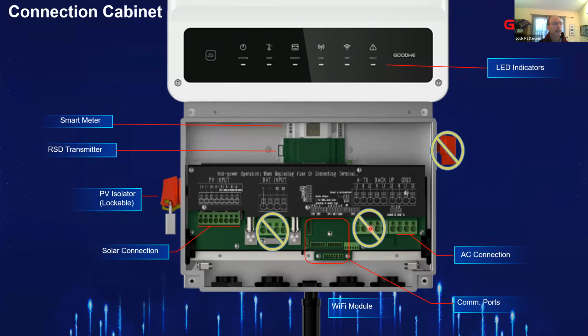Same on the right side. You wouldn't do the AC backup circuit connections. We're only concerned with the AC grid connection on the right. So your L1, L2, neutral. And then for each side, we have grounding equipment grounds. So there's a bus bar here and a bus bar here with set screws. And those are the only times you're using set screws that you have to think about torque. The rest of it is just spring-loaded input terminals. No worry about torque values.